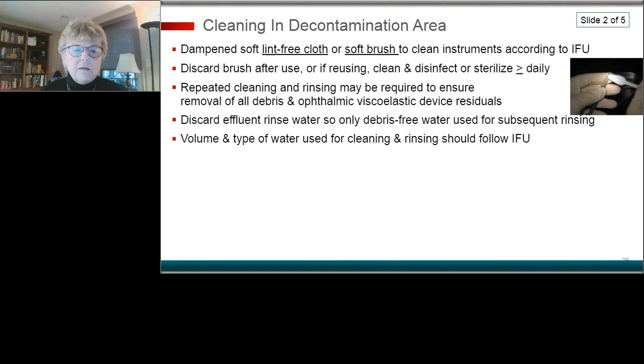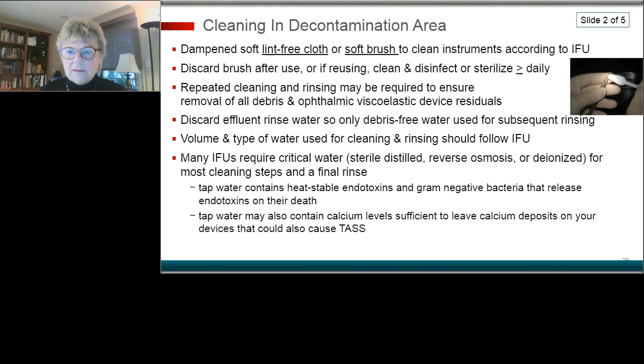depending upon the IFU. Tap water contains heat-stable endotoxins, as we talked about before. They're the dead carcasses of bacteria, gram-negative bacteria that release endotoxins on their death. But they're also present in the water as live organisms. Tap water may also contain calcium levels sufficient to leave calcium deposits in your devices, and that can also cause TASS.